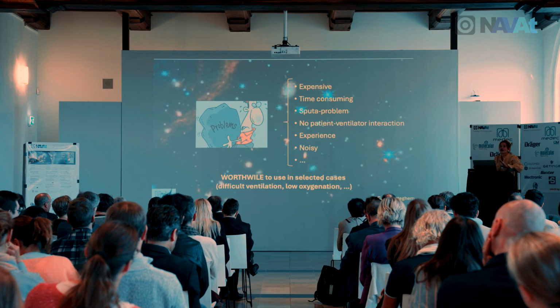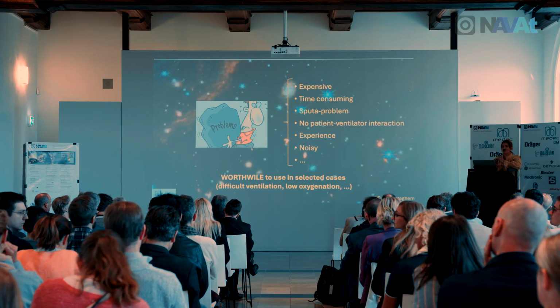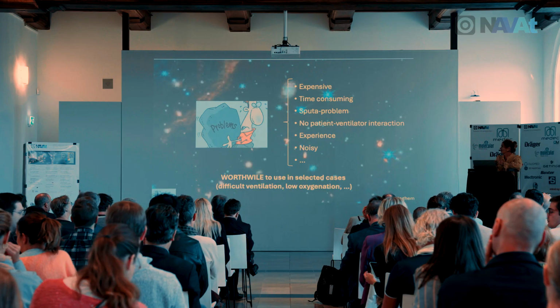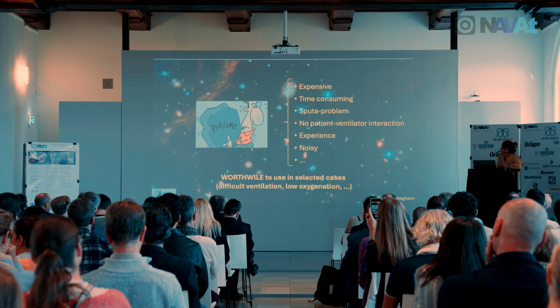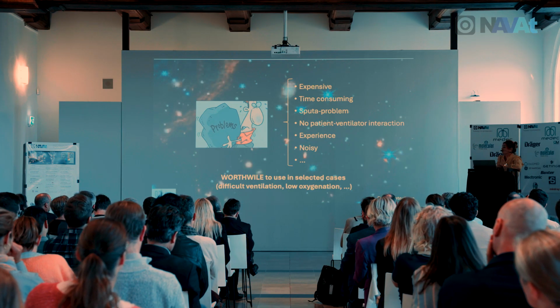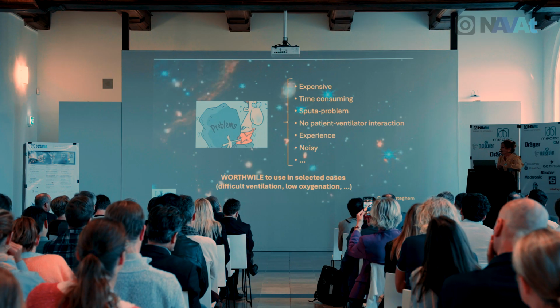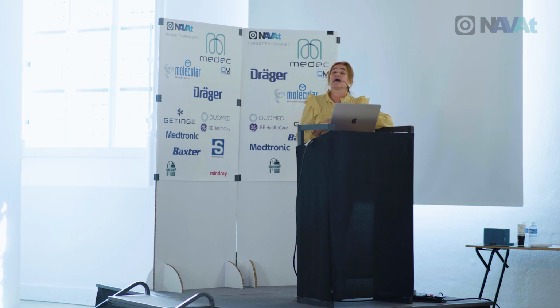When your patient has a lot of sputum, and especially when you use tubes with very narrow lumens, then the tube will be obstructed and the ventilator will switch off. There is no patient-ventilator interaction. You need some experience to use this ventilator. It is also a noisy ventilator. I don't mind, but my surgeons don't like the noise of flow-controlled ventilation.